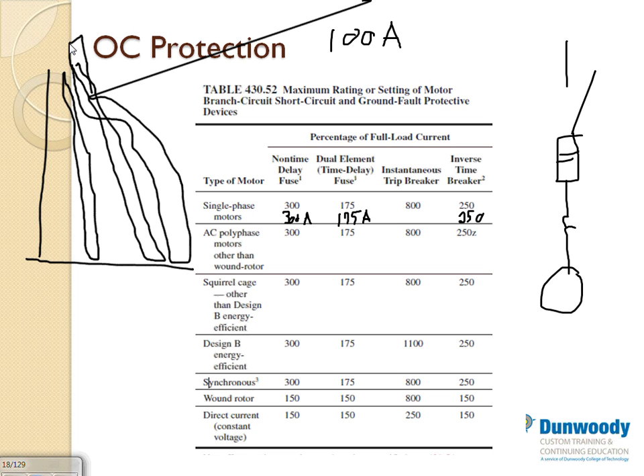This one that you're looking at, the first one, is a non-time delay fuse. You see how it's closer here? It doesn't allow the motor to start. That's why we have to oversize it. It doesn't give enough time for the motor to start. A time delay fuse waits and waits, gives the motor more time to start. Inverse type circuit breakers give it also more time, but it just gives a different shape. All these are basically different ways of tripping. By the way, going this way is the current increase. This is the time characteristic here, current versus time.